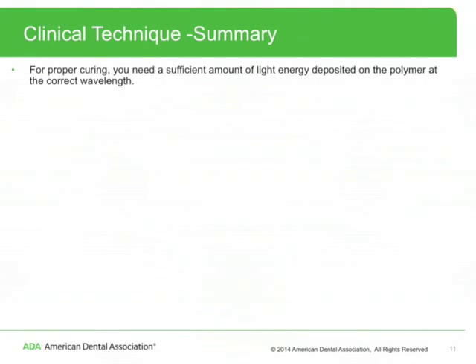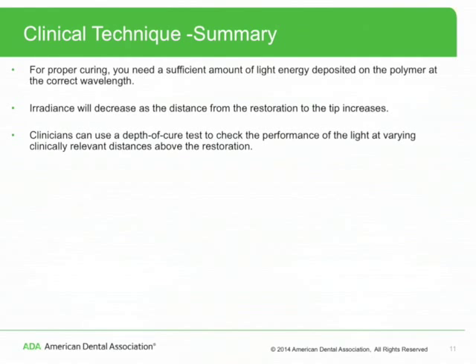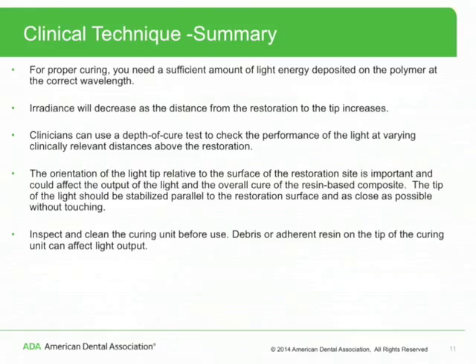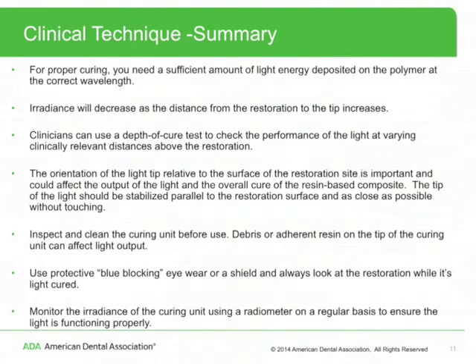In summary, for proper curing you need a sufficient amount of light energy deposited on the polymer at the correct wavelength. Irradiance will decrease as the distance from the restoration to the tip increases. Clinicians can use a depth of cure test to check light performance at varying clinically relevant distances. The orientation of the light tip relative to the restoration surface is important and could affect light output and overall cure. The tip should be stabilized parallel to the restoration surface and as close as possible without touching. Inspect and clean the curing unit before use, as debris and adherent resin can affect light output. Use protective blue-blocking eyewear or a shield, and always look at the restoration while it is light-cured. Monitor the irradiance of the curing unit using a radiometer on a regular basis to ensure the light is functioning properly.